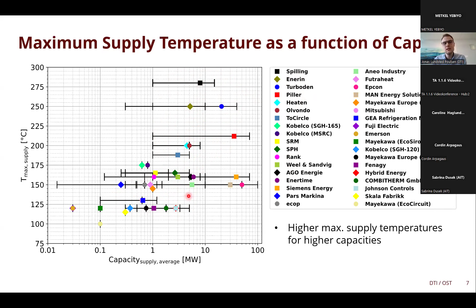This is really quite different technologies we see here. Some of the very high temperatures are systems that are compressing steam. Some of the relatively high temperatures, for instance these, are Stirling heat pumps, and you can see the corresponding dot listed at the highest temperatures. But basically a lot of systems are around 120 degrees and 160 degrees.